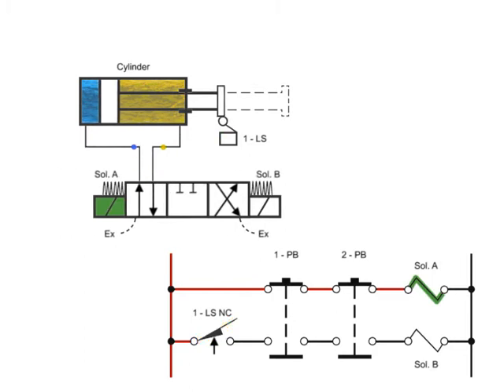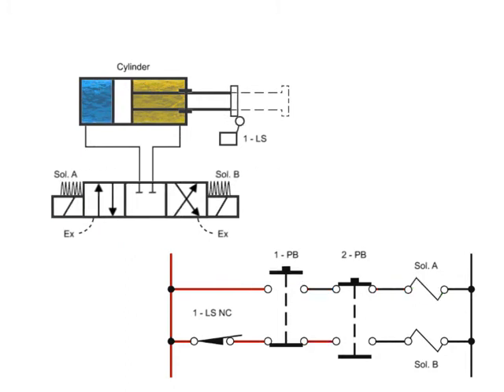When the cylinder begins to move forward, limit switch 1 is released and goes to its normally closed position. If either button is released, both solenoids de-energize and the springs return the valve to its neutral center position, stopping the movement of the cylinder.